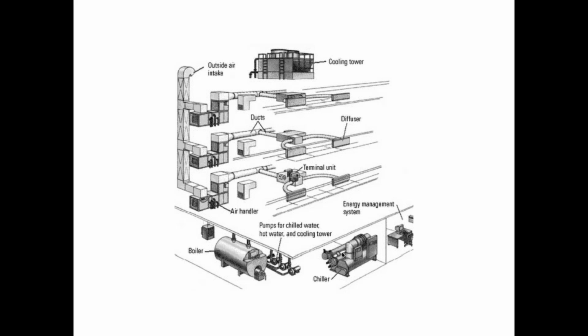Well, some of these units actually use giant banks of coils that they blow air over. That's called an air-cooled condenser. You'll see them on roofs sometimes. But when they're really large machines, that's not practical. You have to have so much space used up for these coils. So in order to take the heat away from the Freon, instead of blowing air over it, they run water over it. So you put water in there, it comes in cold, comes out hot.